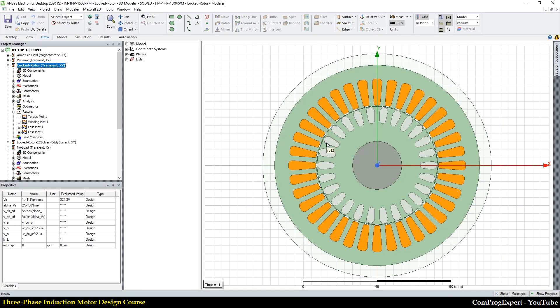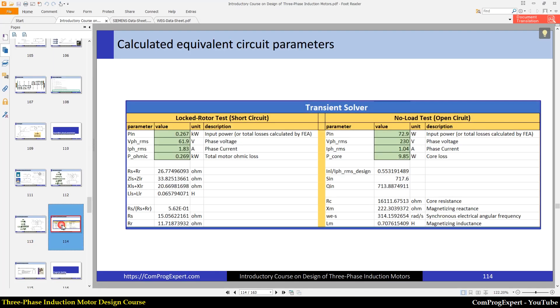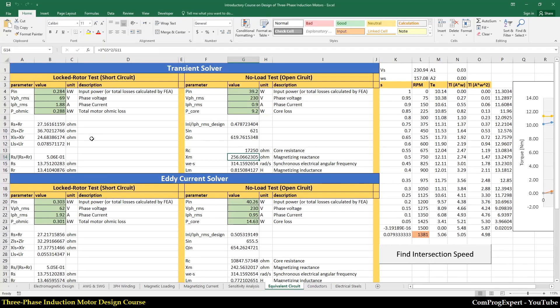In the locked-rotor test, the rotor speed is equal to zero. We apply the phase voltage such that we have the rated current in the stator winding. In this case we can calculate the equivalent circuit parameters. You can see the results — the locked-rotor torque, where the average value of the steady-state waveform equals the starting torque of the motor. Here you can see the equivalent circuit parameters tab.